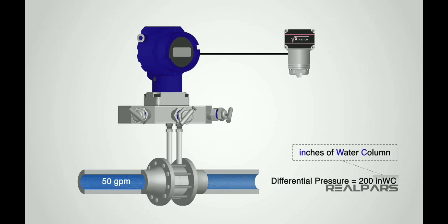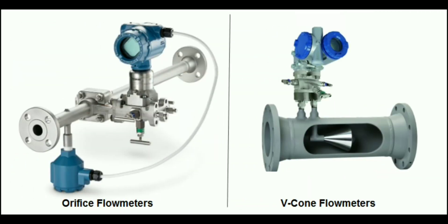Let us look at the working principle of differential pressure measurements. The DP flow transmitter measures the pressure difference, which is delta P, between two points in the flow: upstream denoted as P1 and downstream denoted as P2 of the flow obstruction. This pressure difference is directly related to the flow rate according to Bernoulli's principle and the flow obstruction's design. As the fluid flows through the pipeline, it accelerates as it passes through the flow obstruction and then decelerates downstream, causing a pressure drop. The greater the flow rate, the larger the pressure drop.